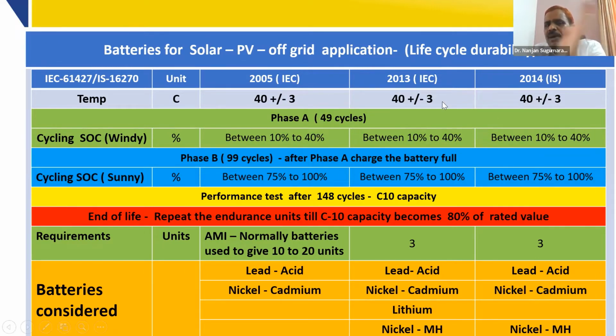Whereas in 2013, in the modified version, they brought lithium into the picture and they made it 3 units. That means the IEC standard itself shows a lithium battery will not give more than 3 units. Whereas in the 2005 version, the manufacturer has to declare, and the manufacturer is declaring 10 to 20 units. Today you take any leading factory catalog, they'll be declaring 10 to 20 units. Whereas here the standard says only 3 units is sufficient. So this itself gives a very clear idea that for the solar off-grid application, tubular lead acid is preferable.